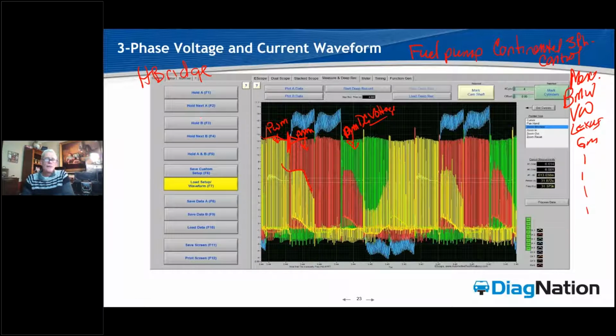Now, remember, yellow is just shut off here. Suddenly, the inductive current and voltage continue to run on that phase. Okay, 2 phases in a 3-phase motor have to be connected at all times in order to keep those magnets pulling in one direction. You're seeing that here.